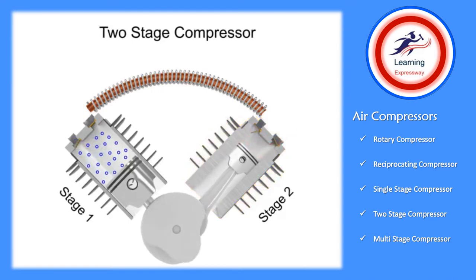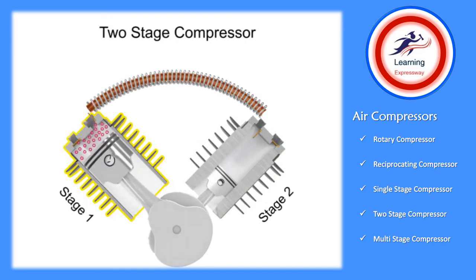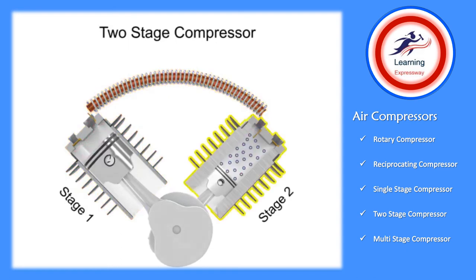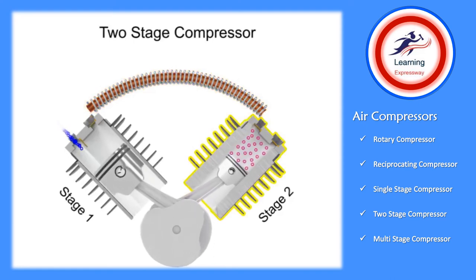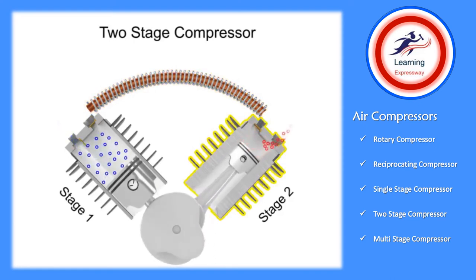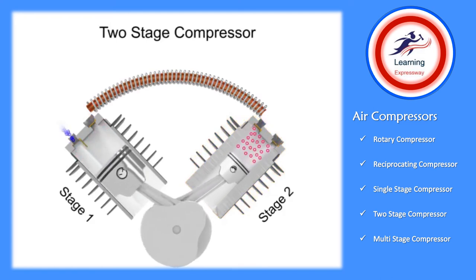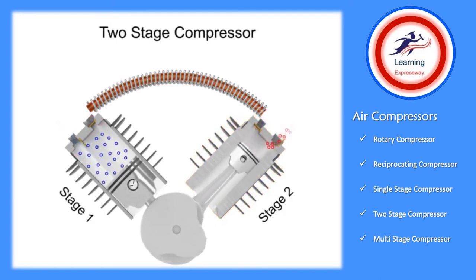The hot compressed air from the first stage is conducted to the second stage through finned tubing, which is exposed to the air from a flywheel fan. After the air is cooled within the tube, the compressed air enters the second stage to be compressed even further. The compressed air entering the second stage is sometimes called supercharged air.